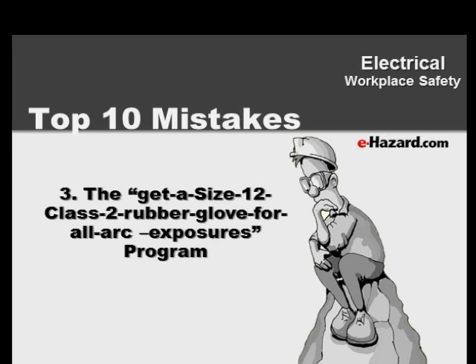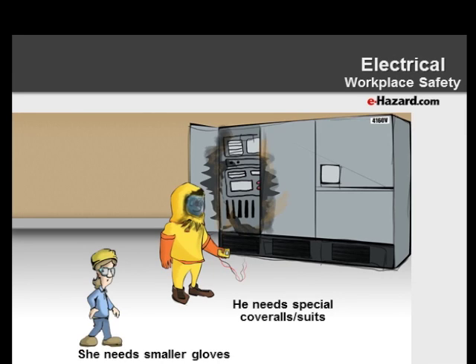Everybody needs a pair of rubber insulating gloves if they're going to do voltage testing. They need to have it for the voltage, close to the voltage that's required. Don't go too many classes above what you're actually doing. And if you're doing high voltage and low voltage, you really need two sets of gloves to make sure you can actually handle the small parts and still be able to do the big work too.